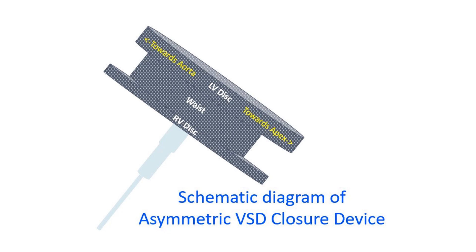The asymmetric VSD closure device is made of nitinol mesh covered with Dacron fabric to facilitate thrombogenesis, so that the final occlusion of the defect is by thrombus formation in the mesh.